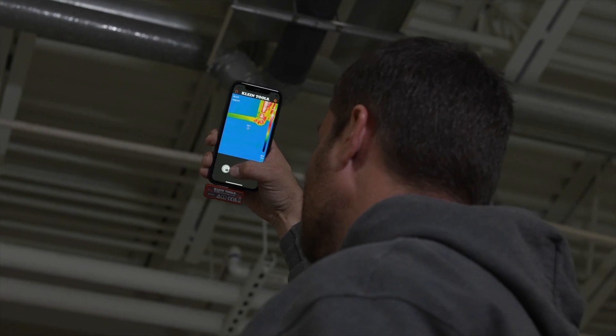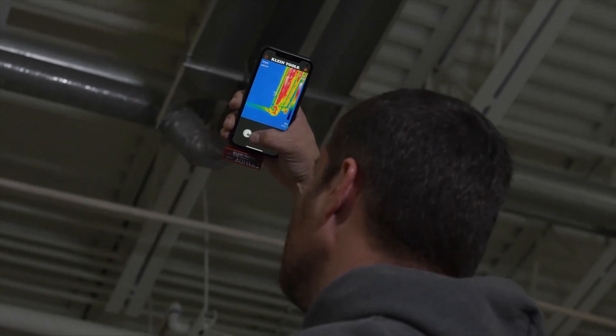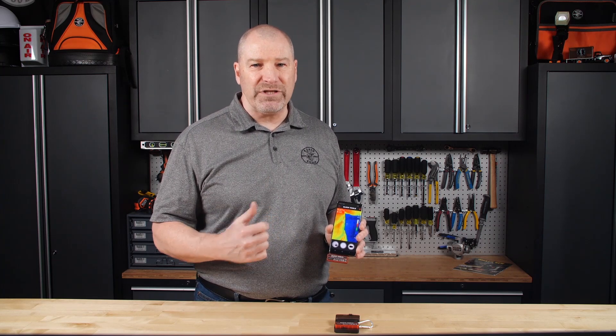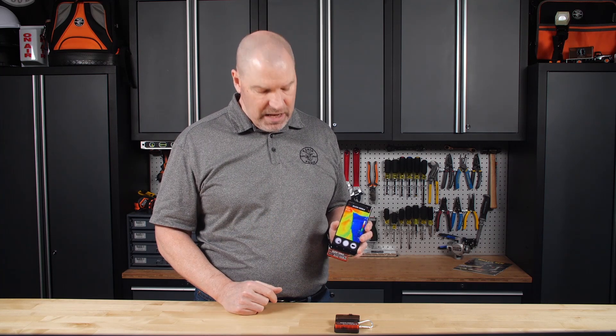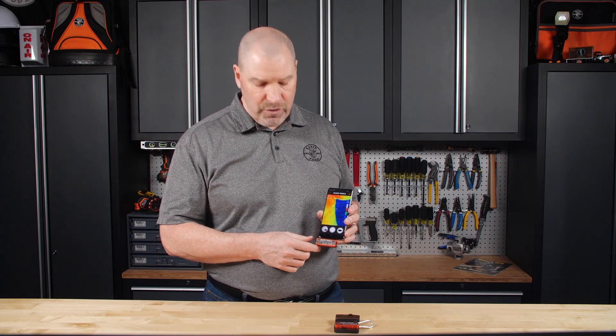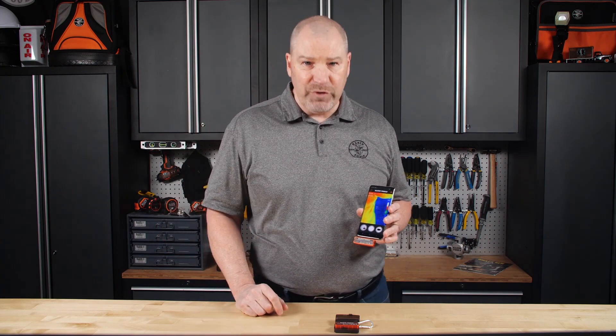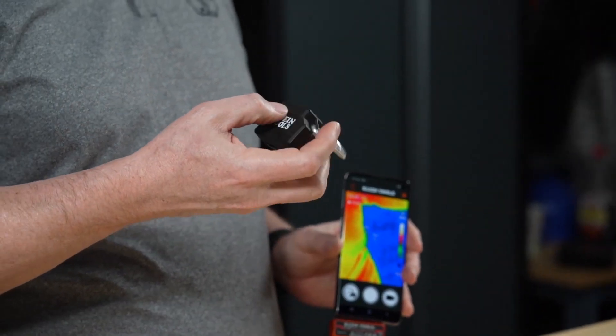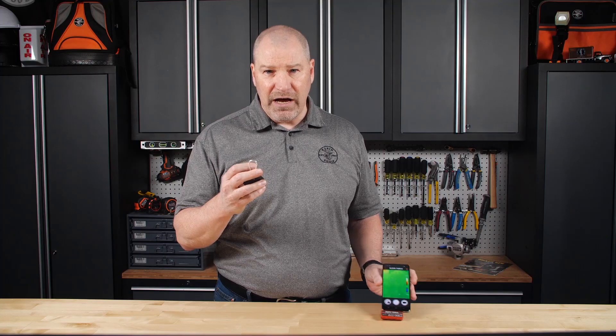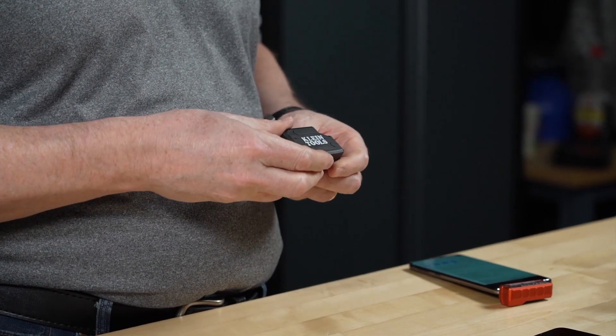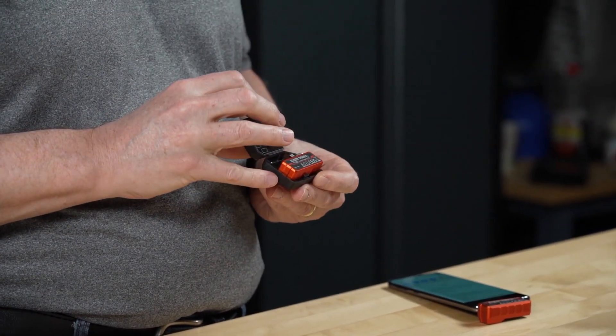The emissivity range is 0.01 to 0.99. The time-lapse interval function is either 4, 8, or 16 frames per second. It also has drop protection from 2 meters, so it can take a little abuse. Both units come with a nice hard carrying case with an attachment carabiner so you can clip it right to your tool bag and have it ready to use.